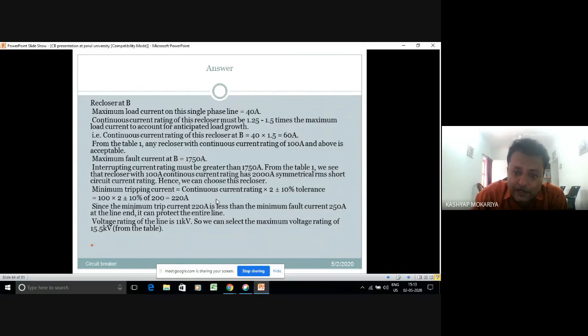Minimum tripping current is the continuous current rating times two, plus or minus 10% tolerance. So what was the continuous current rating as we have gone through in the table? It was 100 ampere, into 2 plus or minus 10%. It means that your minimum tripping current should be 220 ampere. Since the minimum trip current of 220 ampere is less than the minimum fault current which was written in the table, 250 ampere at the line end, it can protect your entire line. So this is how you have to decide the recloser rating for the reclosers available for the system.